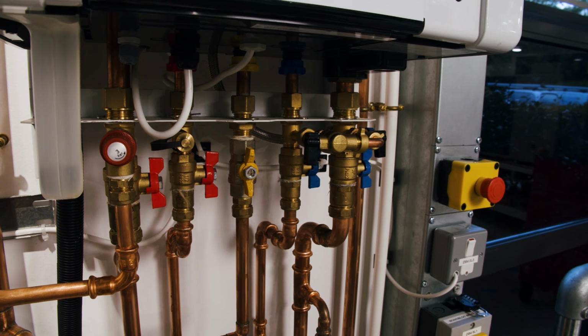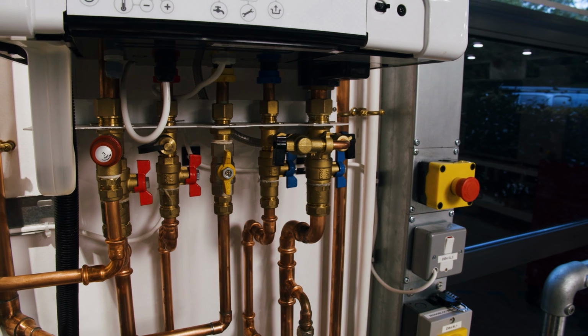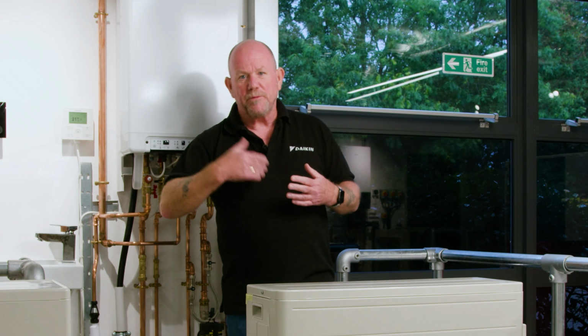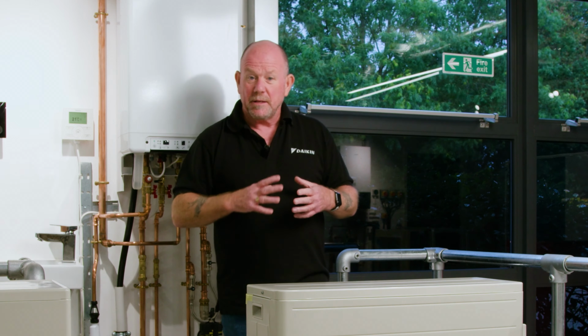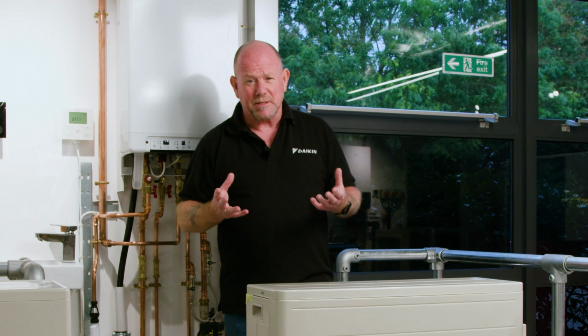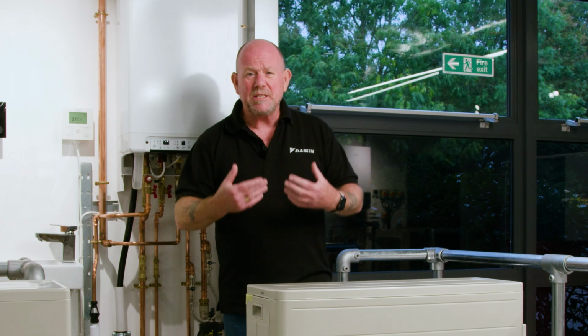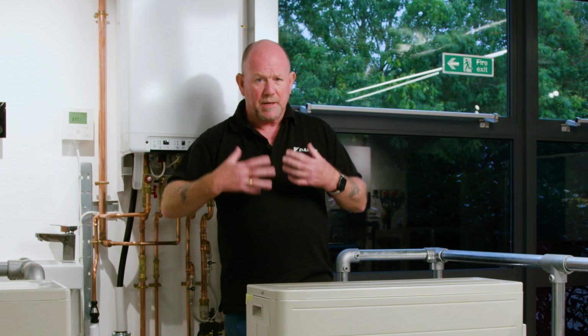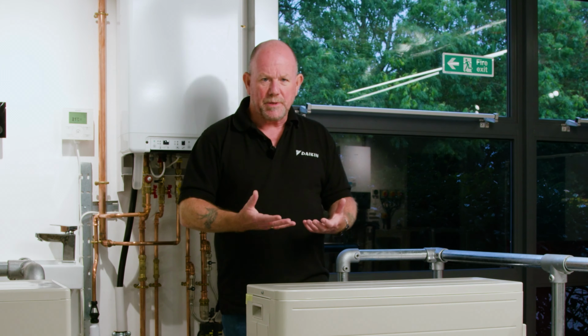As we've already mentioned, the skill set required to install the pipe is exactly the same as you have for a gas boiler. Really, the big difference is we have to consider 2 factors when we install a system like this. We have to consider the free volume of water in the system. So in other words, the amount of water in the system that cannot be isolated from the outdoor unit. We also need to consider the flow rate of the water around the system. Now this probably sounds quite complex, but it really isn't. And again, during the training, we'll show you easy ways to address this to ensure that neither flow nor volume ever causes you an issue.